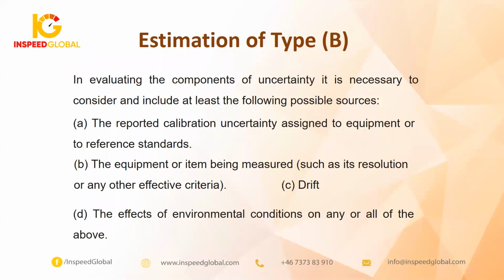The third source is related to the drift. What's the meaning of the drift? You can take your calibration certificate for last year and your calibration certificate for this year, 2019 and 2020 as an example. You take the difference between the uncertainty of last year and the uncertainty of this year, 2019 minus 2020, the uncertainty value mentioned in the calibration certificate. You can use this value as a drift. So this is the third source of uncertainty for type B estimation. The fourth and last one is related to the effect of the environmental condition of your lab, because environmental condition can affect the reading.